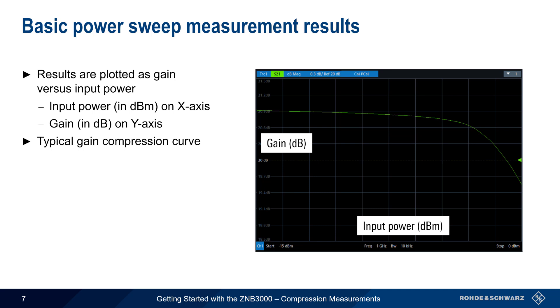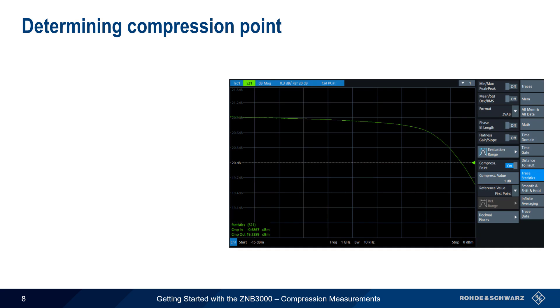The example shown here is a typical gain compression curve. Gain is mostly linear or flat at lower power levels, but decreases or rolls off as input power increases. The ZNB3000 can also automatically calculate compression points from the trace. This is done by pressing the Trace hard key, selecting Trace Statistics, and then enabling the compression point measurement. The default value is 1 dB but can be modified by the user. Once enabled, the compression point measurement automatically calculates both the input and output compression points and displays them on screen.